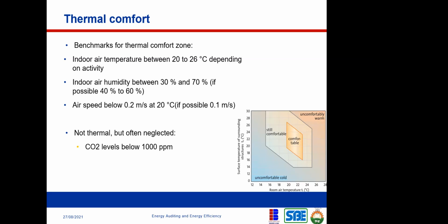Now we advocate that when you're running your air conditioning system, close your windows, close your doors. But I'm not saying that it couldn't lead to a problem. So for this kind of situation, occasionally you need to just open up the windows so you can have more cross ventilation, expel some of the CO2 and bring fresh air into the space. And we also need to understand how our air conditioning system works. Some of us are of the opinion that our air conditioning system takes air from outside, cleans it, makes it cold, and throws it inside our space. No. An air conditioning system takes the air inside our space, cleans it, makes it cold, and throws it back into the space. So it's not taken from outside, except for certain configurations where you have an economizer.